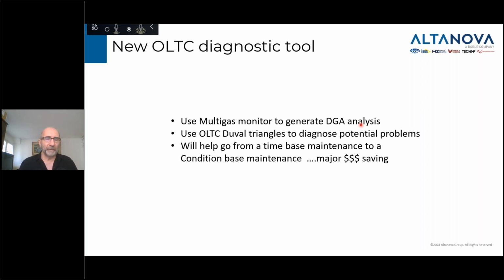So, I know we've worked with some customers in the Americas that were really focusing on getting away from the TBM to a CBM system with some major cost saving. And one way of doing it is naturally doing it like the main tank. You take regular oil sample, you send it to the lab. But also we've seen customers in the Americas and the Asian Pacific starting to install online monitor systems that do exactly what we do for the main tank. They're doing it for the OLTC by measuring continuously the DGA and then using specific diagnostic software to do your diagnostic. So it's a trend that's coming. We think that mostly in the next few years, we're going to see more and more customers starting doing that.